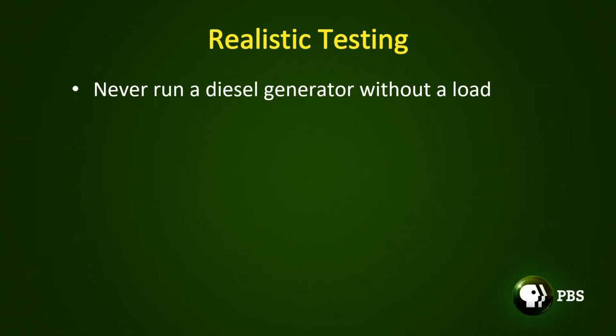And the other thing that it can do is, if you're out in a remote area and the generator has wet stacked and it does start, it'll start blowing out chunks of carbon that are on fire. And that can cause a brush fire quicker than anything. And that's not going to do you any good. So try to avoid ever running a diesel generator without a load.